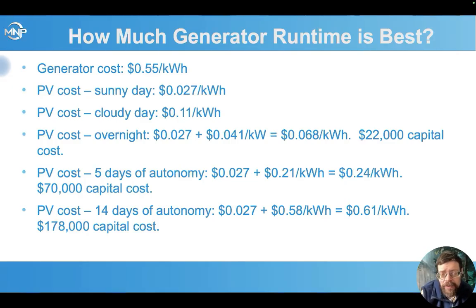However, look at how the capital costs are going up for the PV and battery system. It's not just amortized costs over those 20 years. Sometimes it's also what capital costs can we deal with. Because with the PV and the batteries, we're paying everything up front, whereas with the generator, a large portion of that is going to be in fuel cost, maintenance costs, which we didn't even include in that 55 cents per kilowatt hour, and replacement costs of that generator. It's probably not going to last that entire 20-year lifespan that everything else is, so you're going to be replacing it a couple times along there, whereas with the PV, all that capital cost is up front.